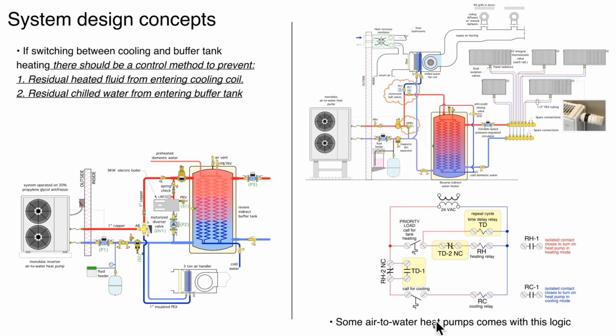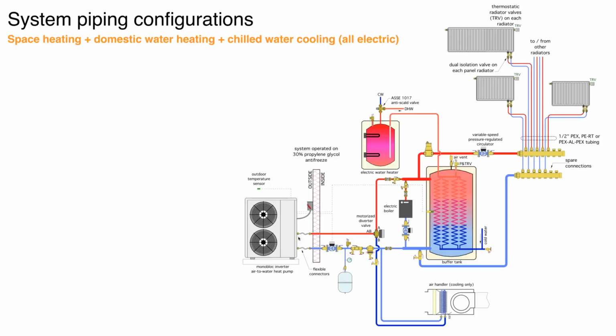And I do want to point out that some heat pumps that are out there have this logic built in. They have this transition logic so they don't end up sending hot slugs into a cooling coil or cool slugs into a buffer tank or some other load that is expecting hot fluid. So that's something you want to address as you design a system. Now let's run through a few example systems, and let me just check on time here. We should have a little time for questions.